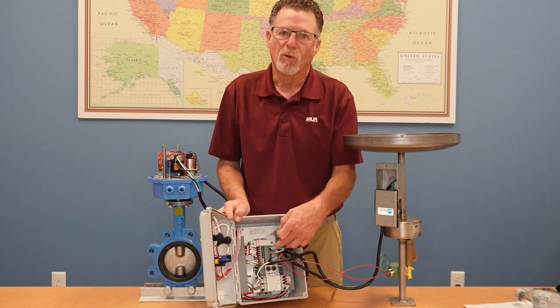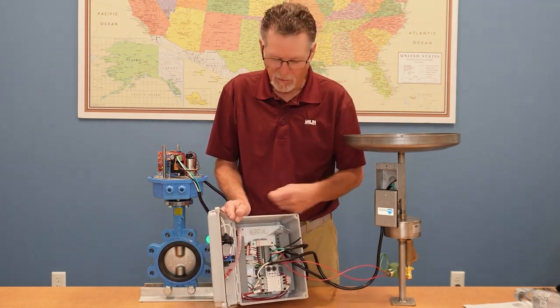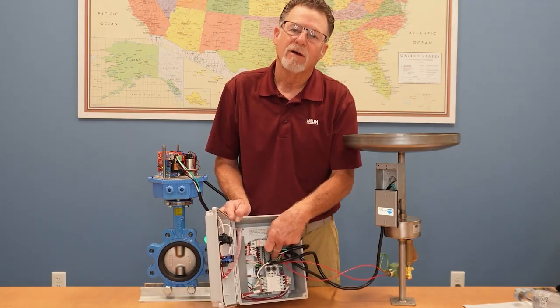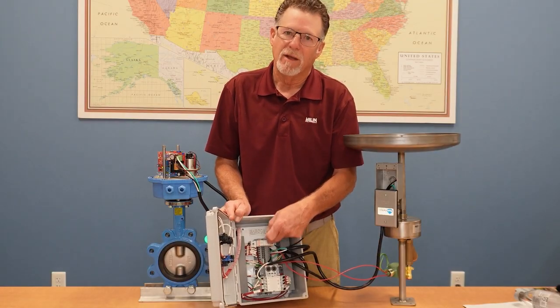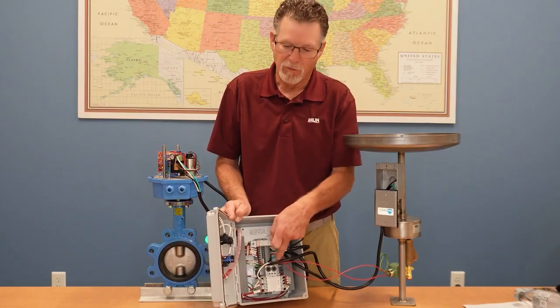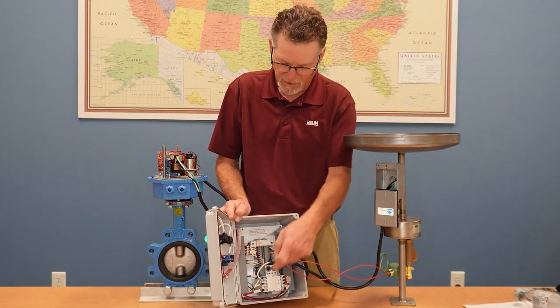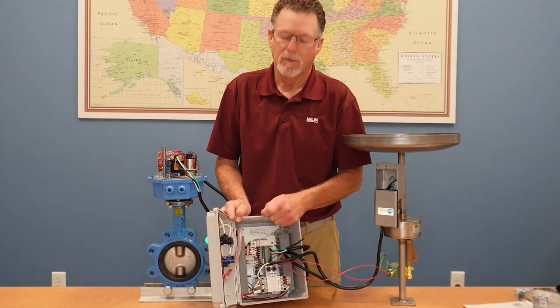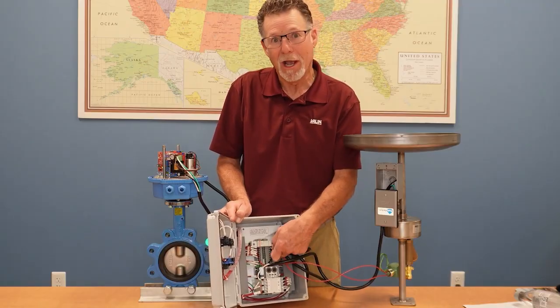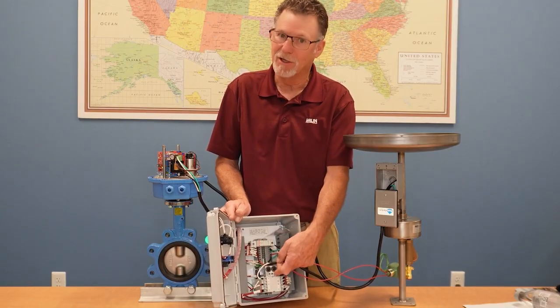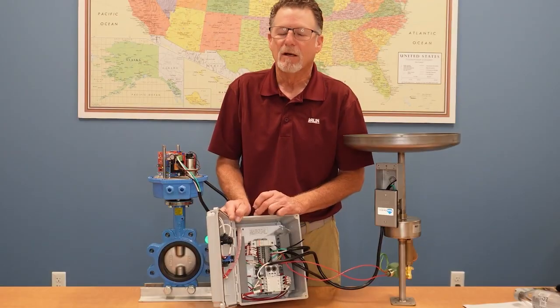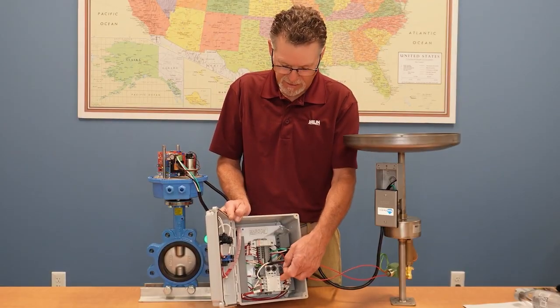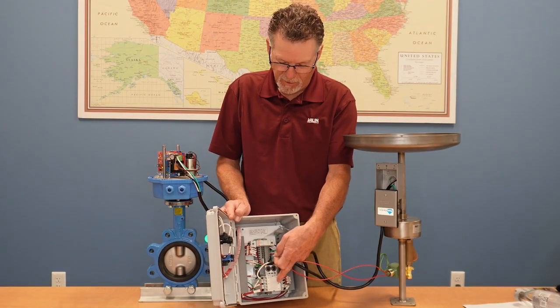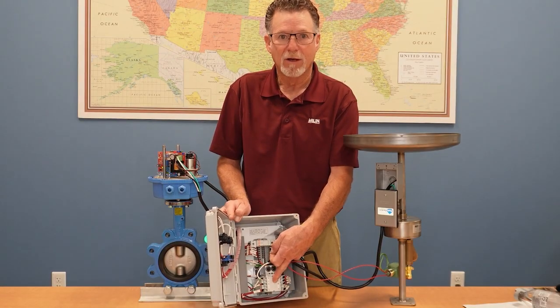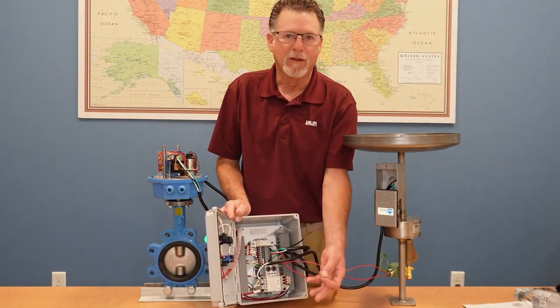So in the normal condition of where it's sitting right now, we should have 120 volts on terminal 8 and nothing on 9. If you have voltage on both 8 and 9, you've got a bad relay. If you have voltage on 9 and not 8 in this condition, you probably have a bad relay. Usually what you'll see is you might have voltage on 8 right now. You go ahead and jump it and nothing happens.